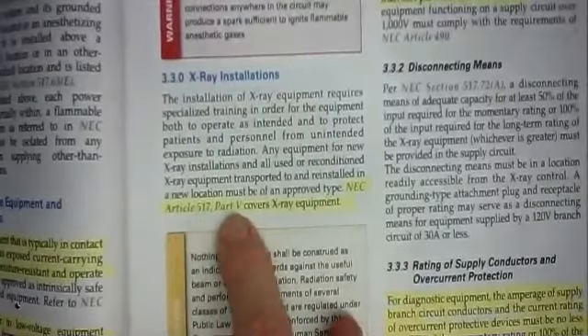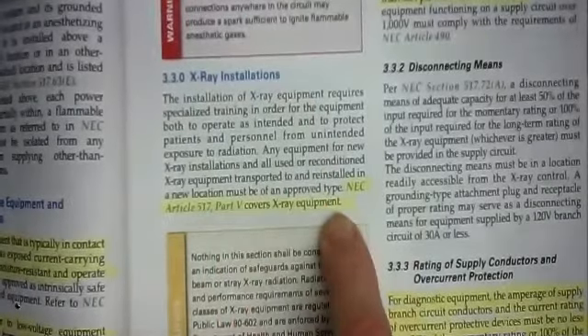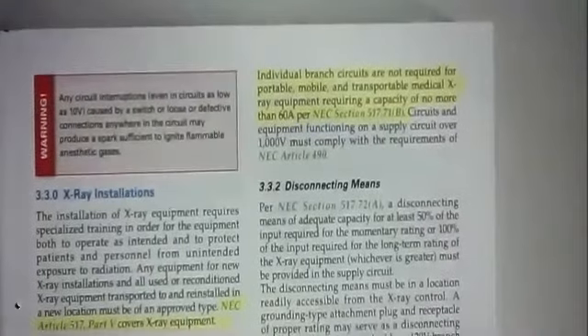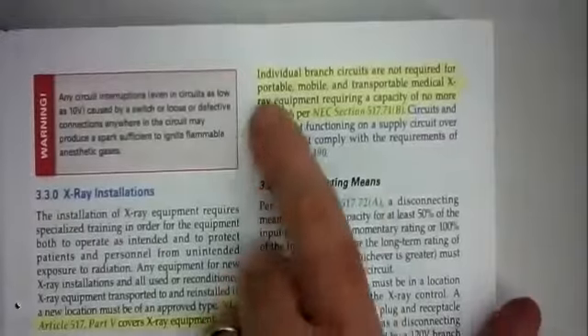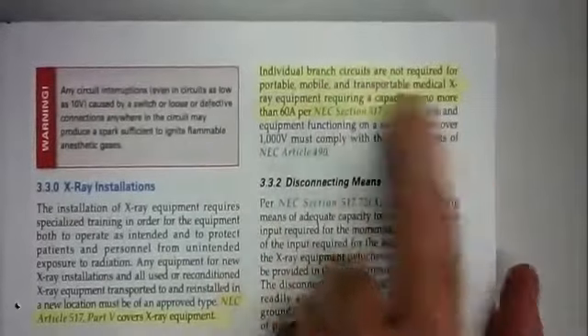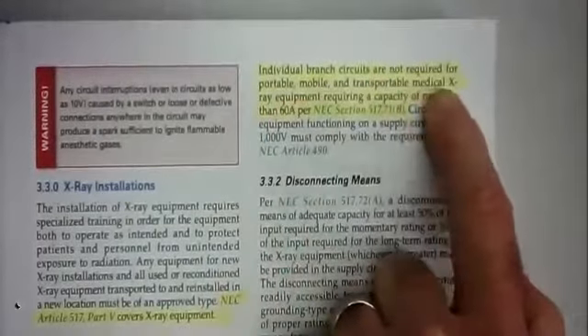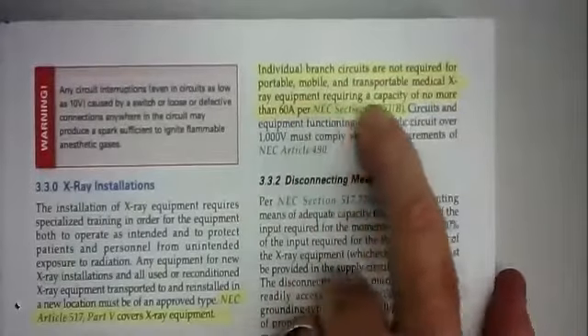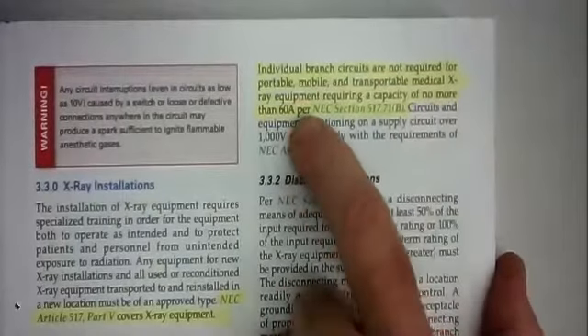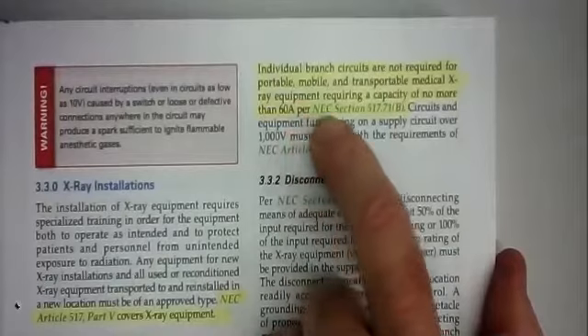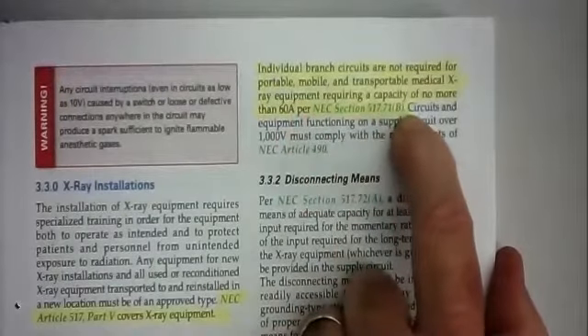Over on page 21 on the left-hand column, they're talking about X-ray equipment installations. NEC Article 517 Part 5 covers X-ray equipment. And the top of the right-hand column on page 21 says individual branch circuits are not required for portable, mobile, and transportable medical X-ray equipment requiring a capacity of no more than 60 amps per NEC section 517.71(B).